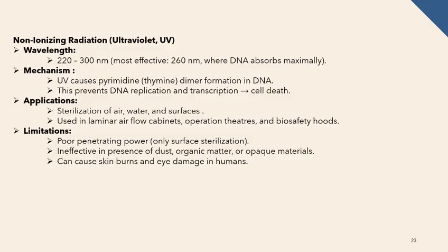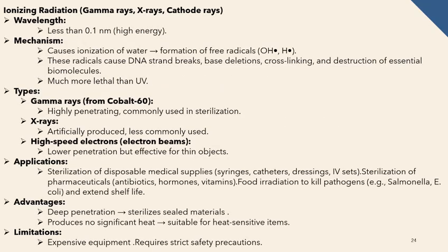The next is ionizing radiation, which includes gamma rays from cobalt 60 or cesium 137, X-rays, and electron beams, which ionize water and other molecules and produce free radicals. These free radicals cause DNA breaks, protein damage, and membrane disruption in the microorganism and lead to its death.